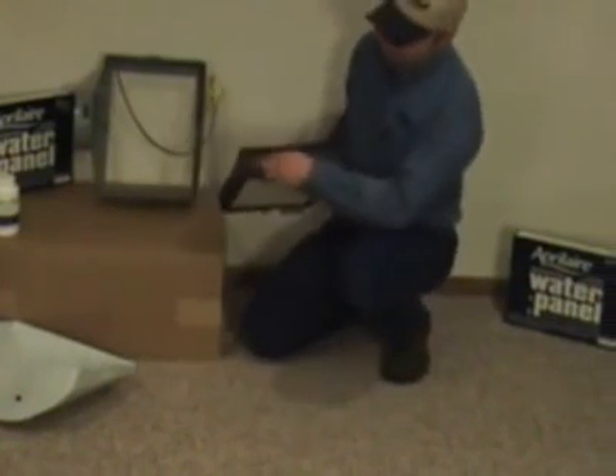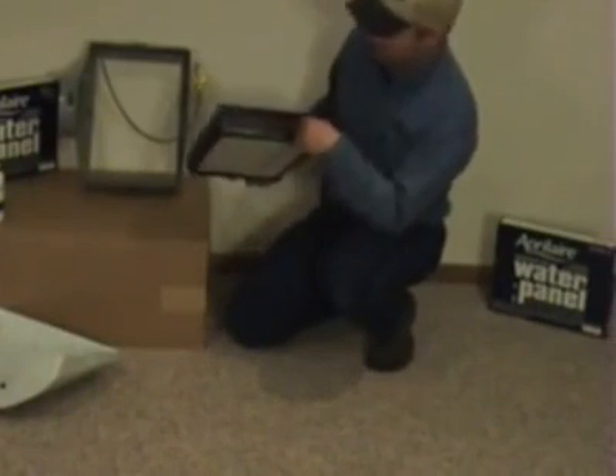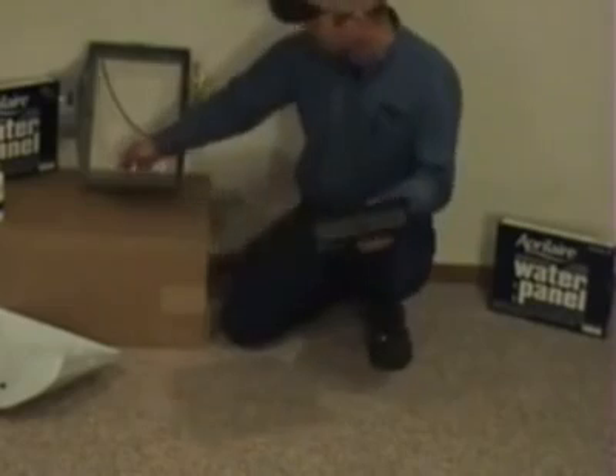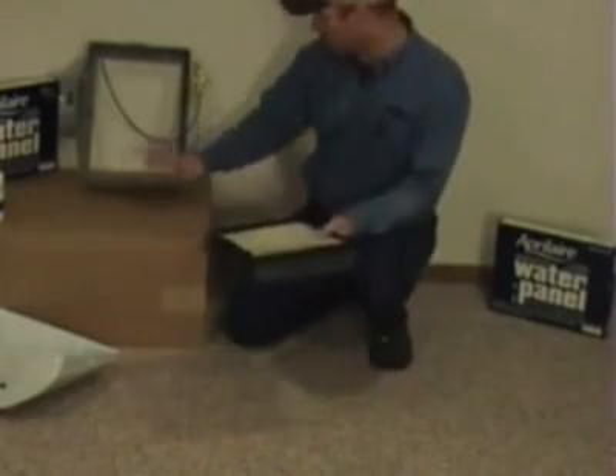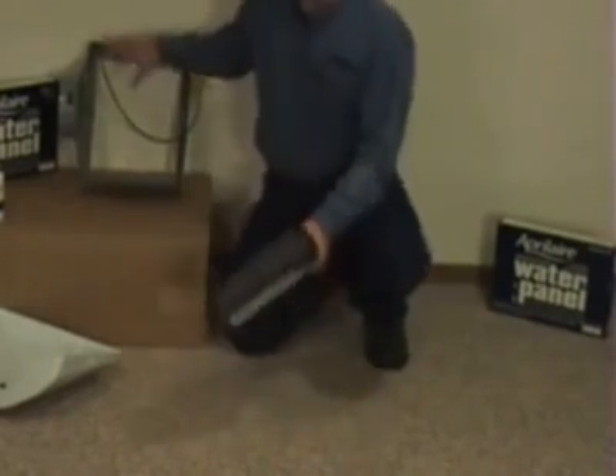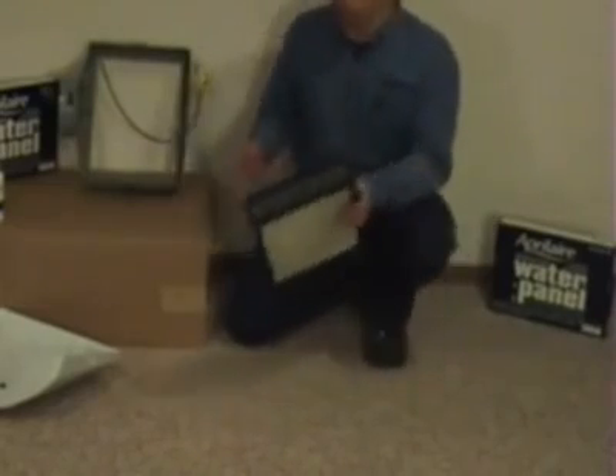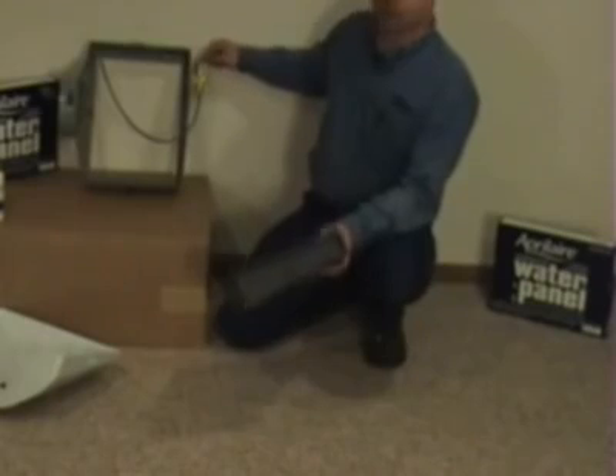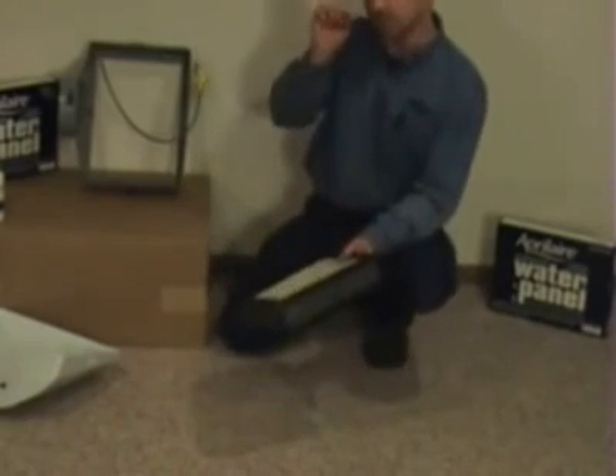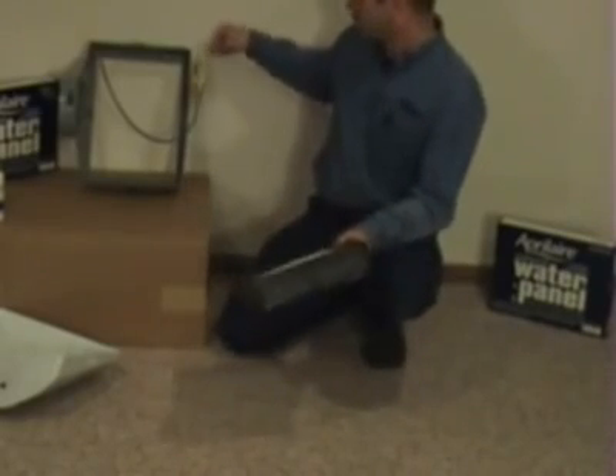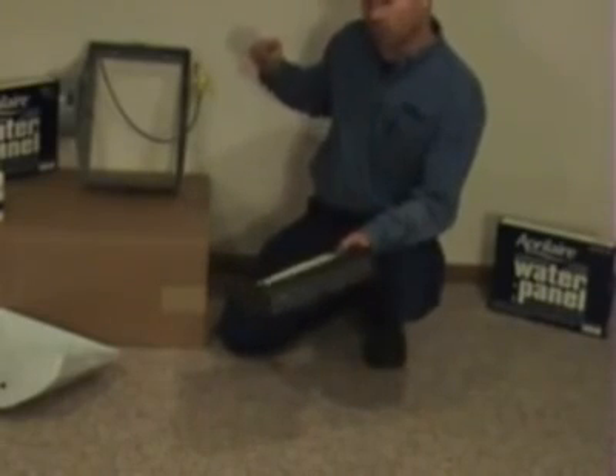Again, kind of inspecting it and making sure that all of your water distribution ports here are open and that your drain is open. There's a drain that goes down through the bottom, make sure that that port is open. One of the big reasons humidifiers fail to work is that there's a little water orifice on the incoming line. Sometimes you need to take a little pin and clean that out. And if you take this apart, you'll usually find that small orifice.